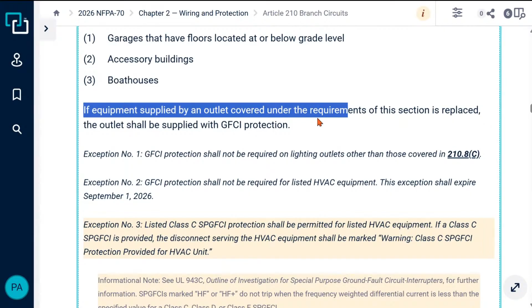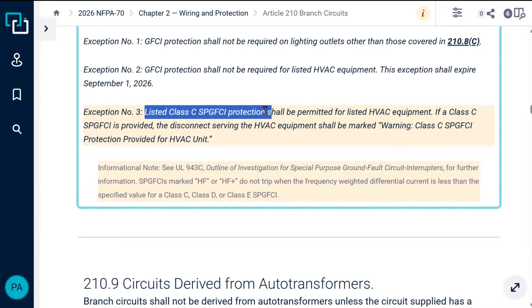So then you have exception number 3. So this is what introduced a listed Class C SP GFCI protection. Okay, so let me clarify first. You have your normal GFCIs, your normal Class A GFCIs. Basically, we refer to those as 5 milliamps nominal, but they're actually under 5, 4 and less, they're not supposed to go off. 6 and greater, they're supposed to activate. So we call it 5 nominal. It allows the manufacturers to have something to shoot for.